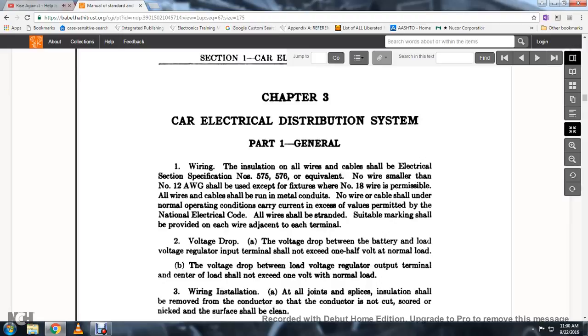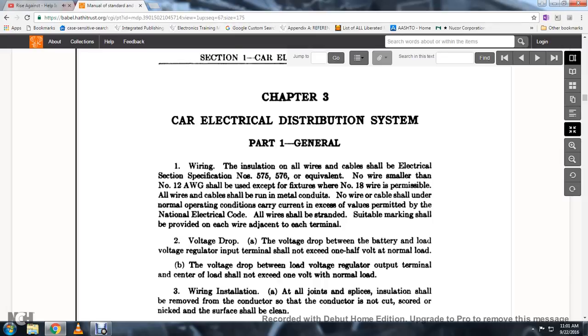Wiring: The insulation on all wires and cables shall be Electrical Section Specification Nos. 575, 576, or equivalent. No wire smaller than number 12 AWG shall be used except for fixtures where number 18 wire is permissible. All wires and cables shall be run in metal conduit. No wire cable shall under normal operation carry current in excess of the value permitted with the National Electrical Code. All wires shall be stranded with suitable marking provided on each wire adjacent to each terminal.